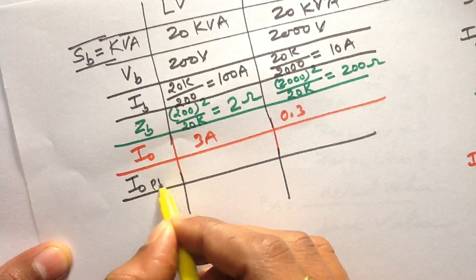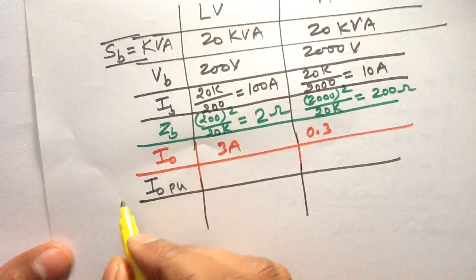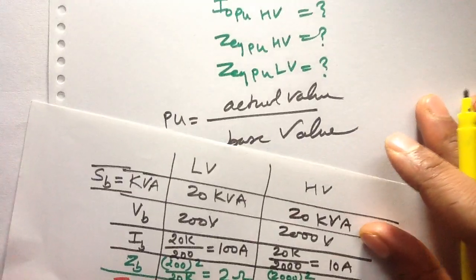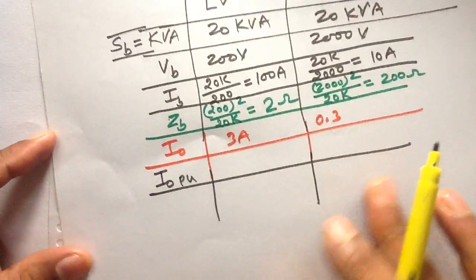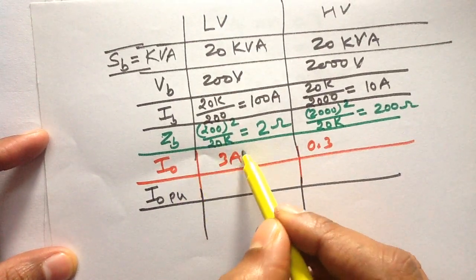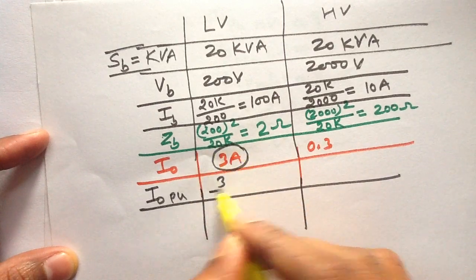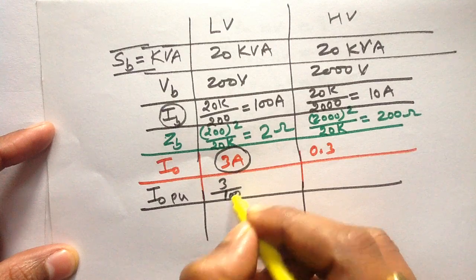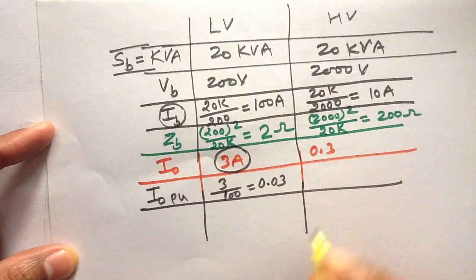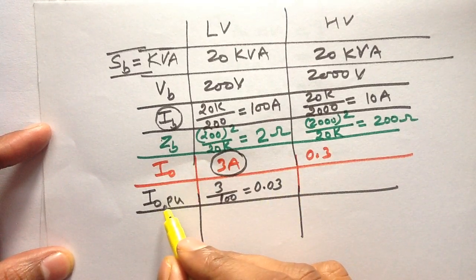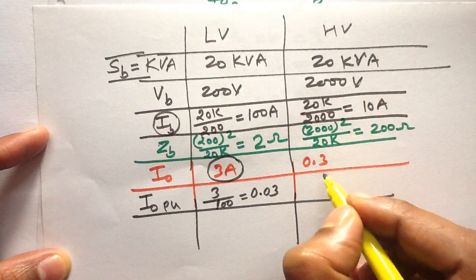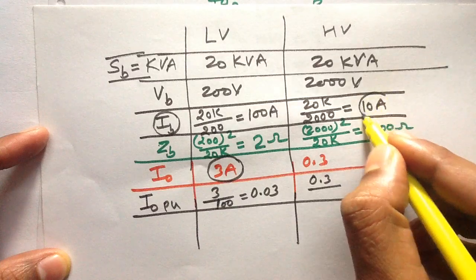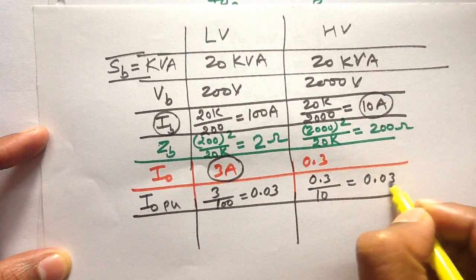The exciting current in per unit on LV side: per unit value equals actual value divided by base value. The actual value of the exciting current on LV side is 3 Ampere and the base value of the current on LV side is 100 Ampere, so it will be 0.03 per unit. The exciting current on HV side in per unit: actual value 0.3 Ampere divided by base value 10 Ampere also gives 0.03 per unit.